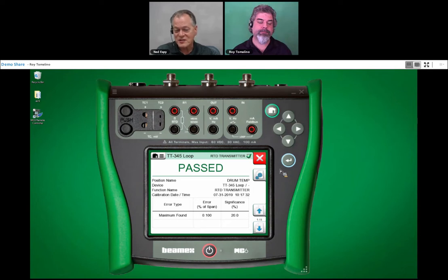Yeah, but we've also made many presentations saying it's not good to adjust every time. In this case, it's only 20% of the way out, and it could be because it was installed on a cold day in Colorado, and today it's a nice, beautiful ambient temperature day in Colorado. So it could be off just due to environmental conditions, or just the conditions of that day. You could go out a month from now, and it's out by minus 10%. It's moving back. It's going up and down, which is good if it's staying within your tolerance.